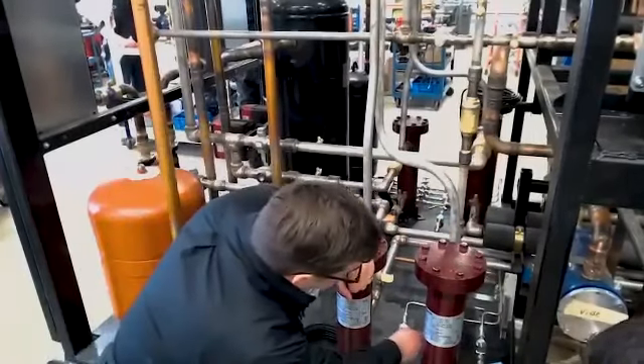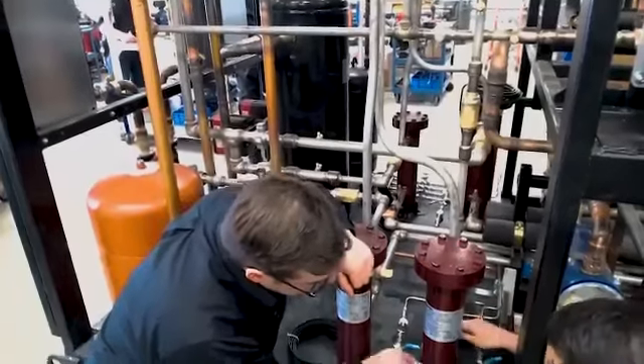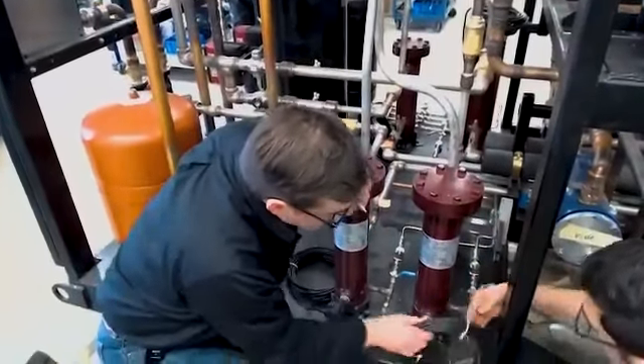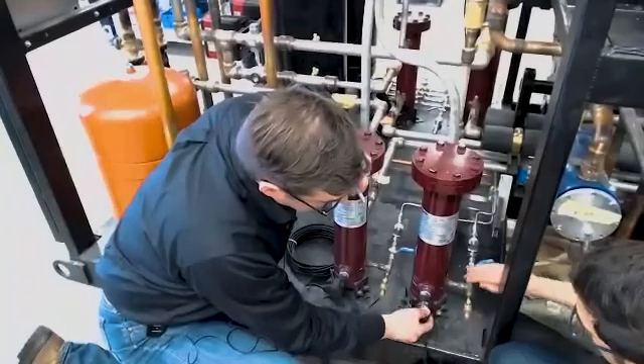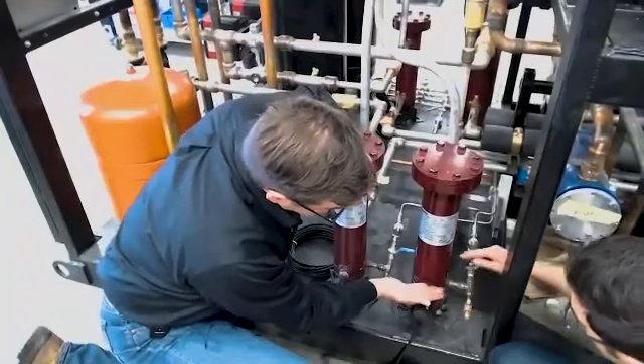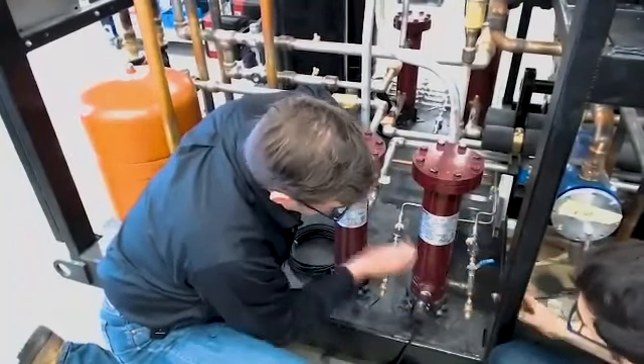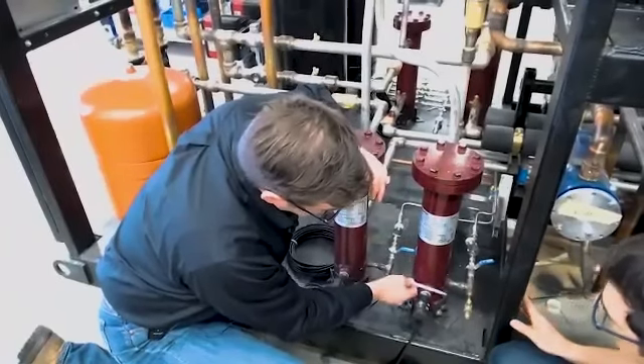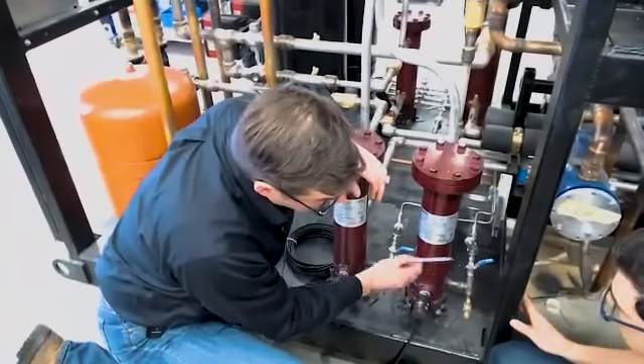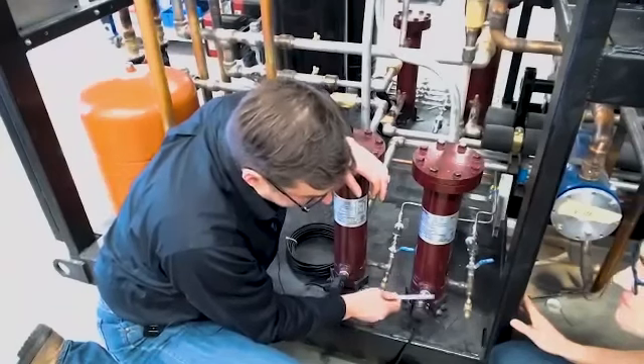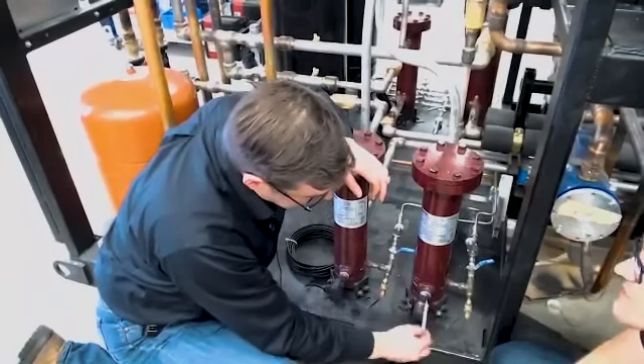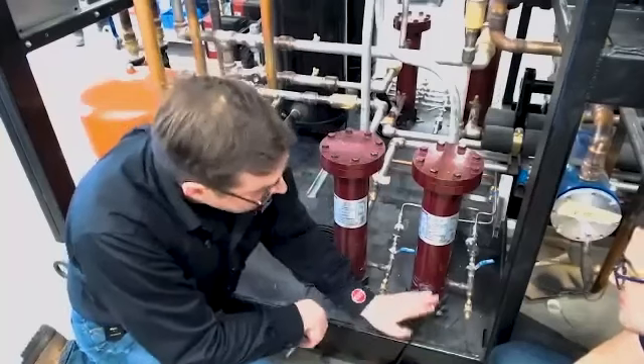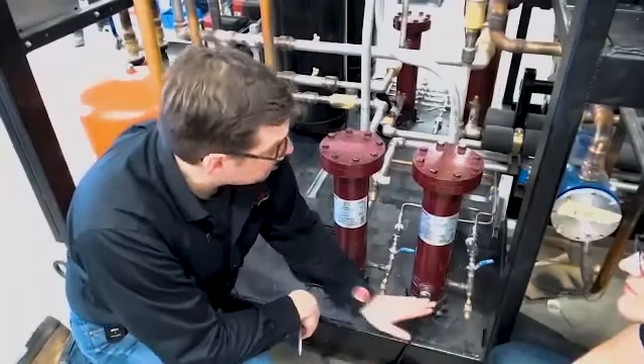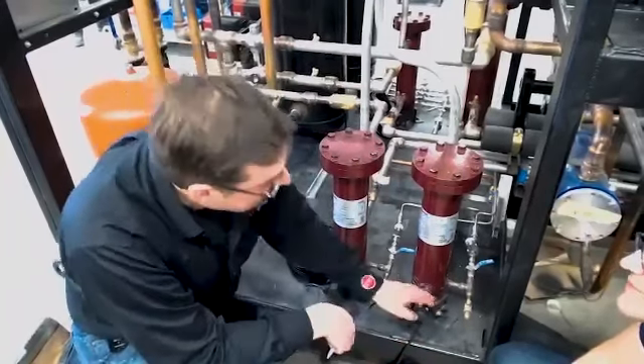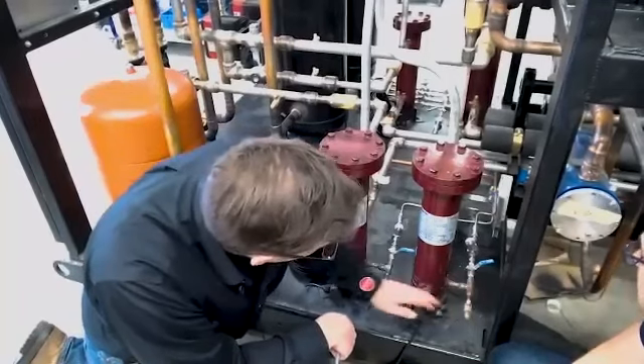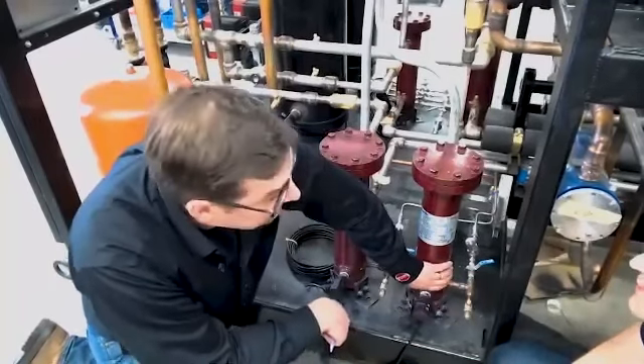Okay. So we have our supply line coming in here. This is an on-demand. So the first step that you're going to see is we got a photo optic eye here. As the gas passes through, the oil reservoir is going to begin to fill with oil. A continuous demand for oil will not have this photo eye. You just have a sight glass here. The specific design sends a signal back to the controller, and then the controller opens up a block solenoid, now allowing that to bleed the oil from the oil separator.